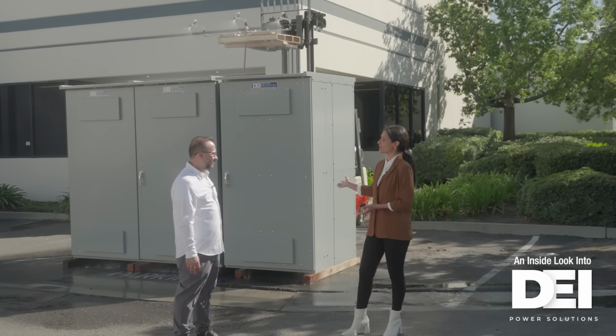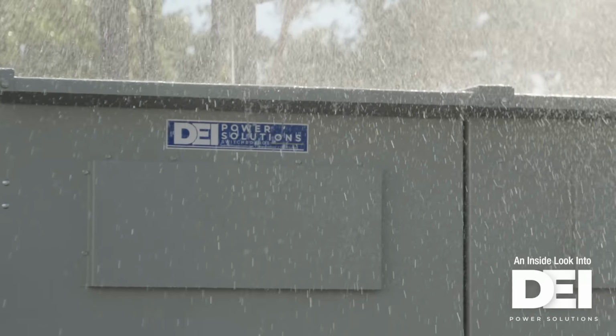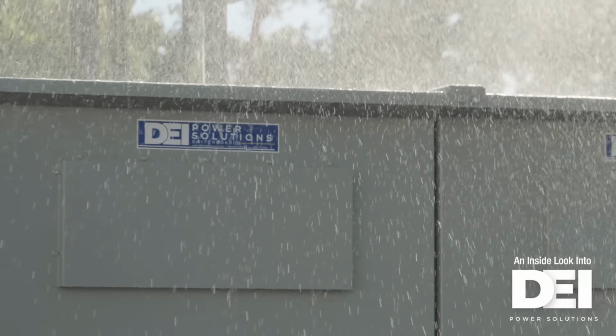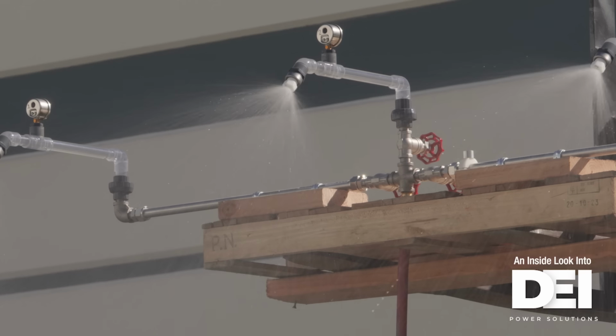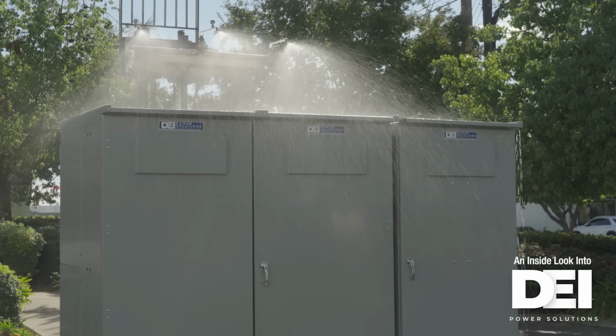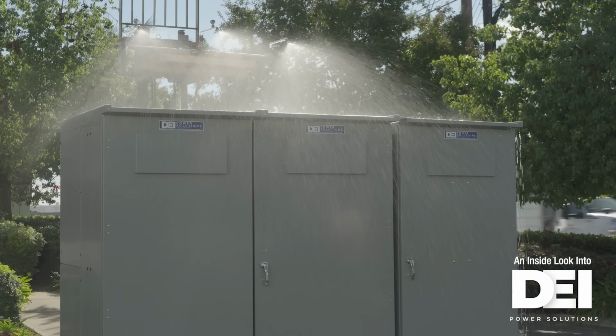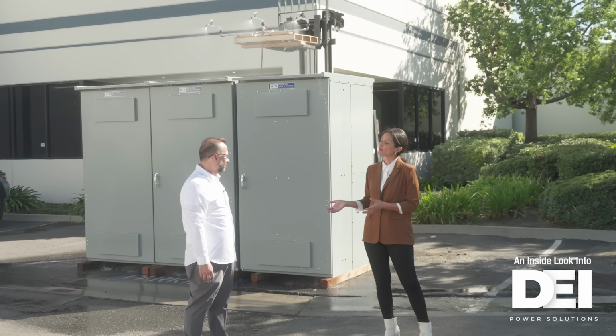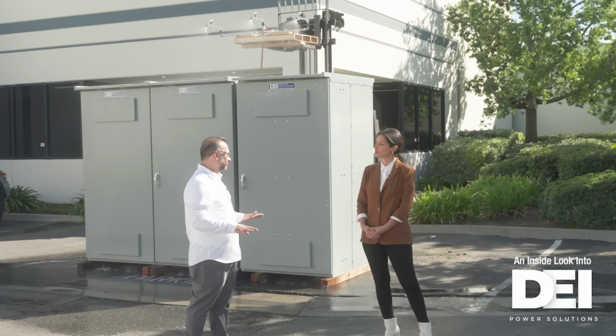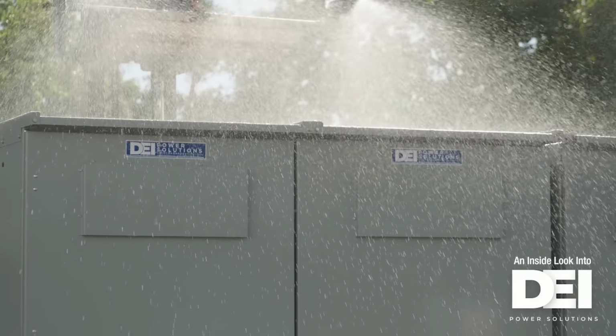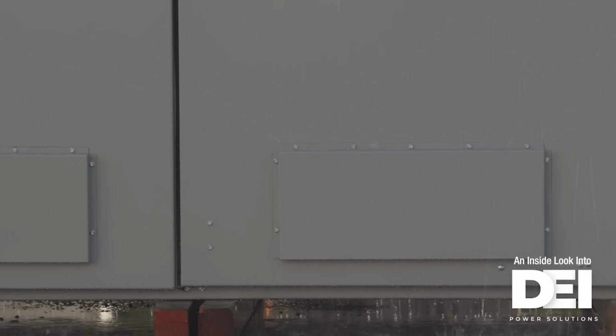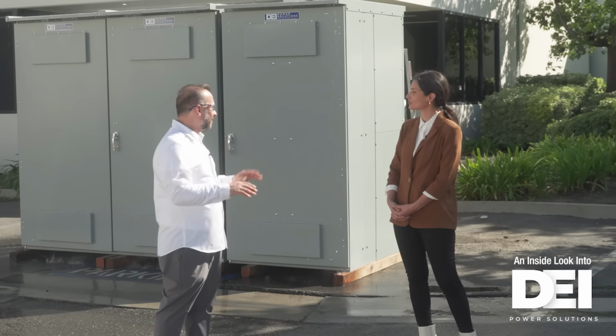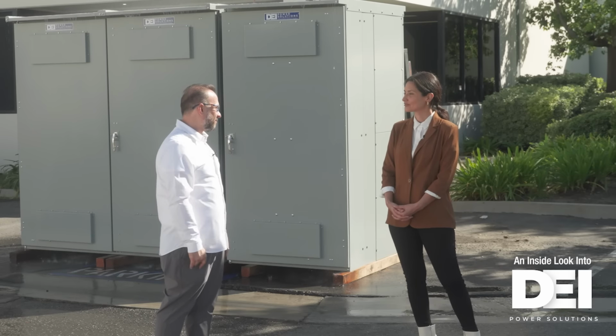So what exactly do we have happening here? Well, we're duplicating rain. Per UL 891, they require us to use a testing apparatus. We will let that rain test go for 60 minutes per side. So what exactly are you looking for in the test? We're looking to make sure that there's no water touching any live parts. After the 60 minutes per side, our inspectors will go in, check it, and make sure no water is on any live parts.